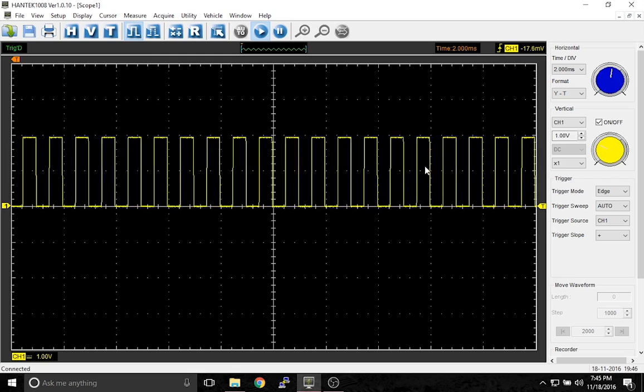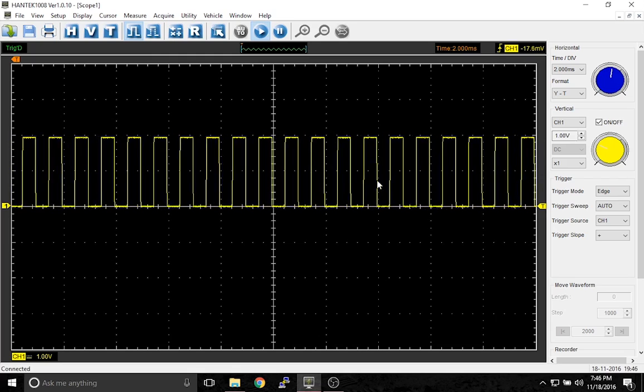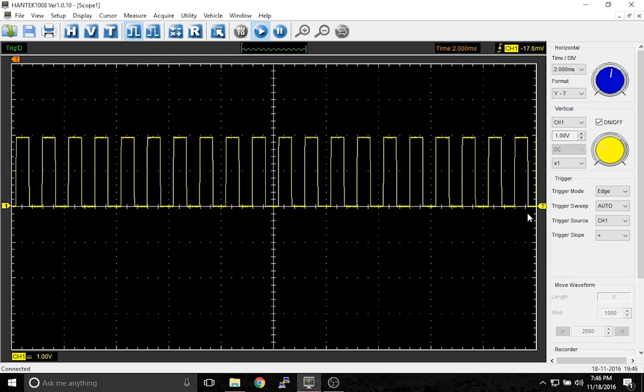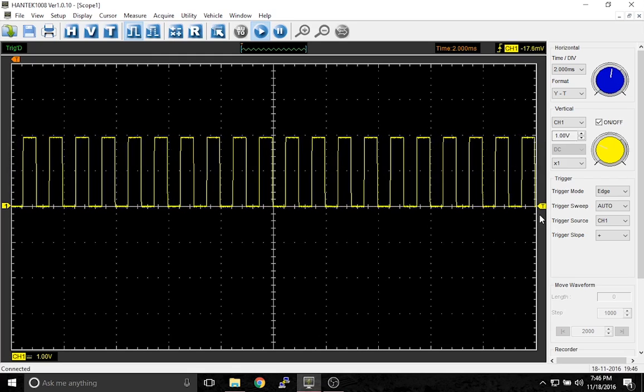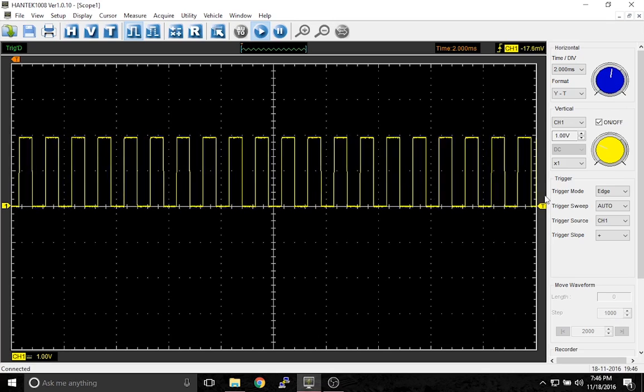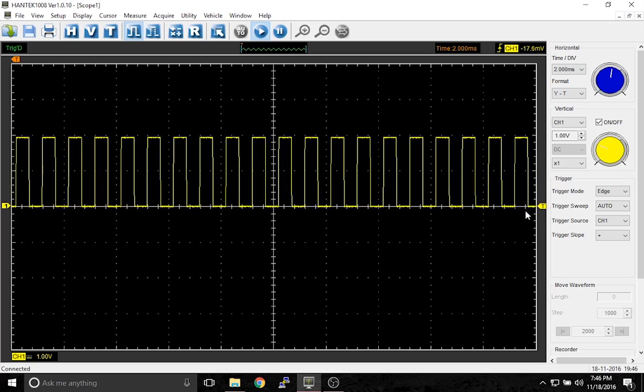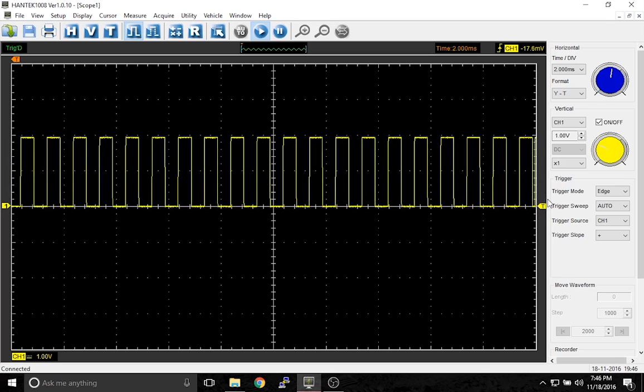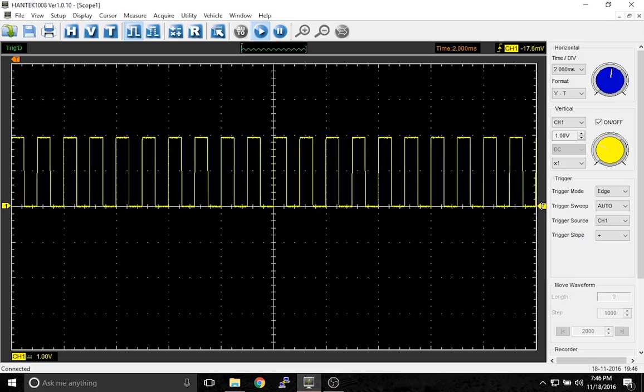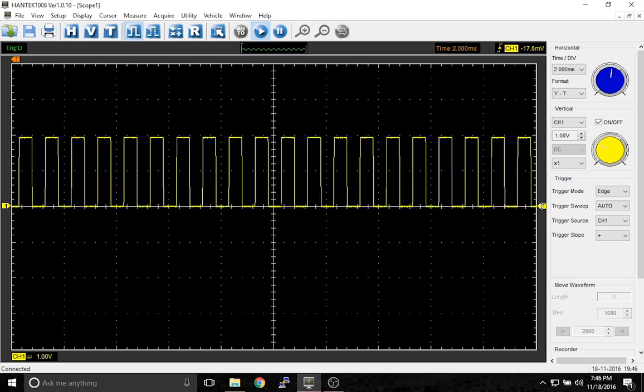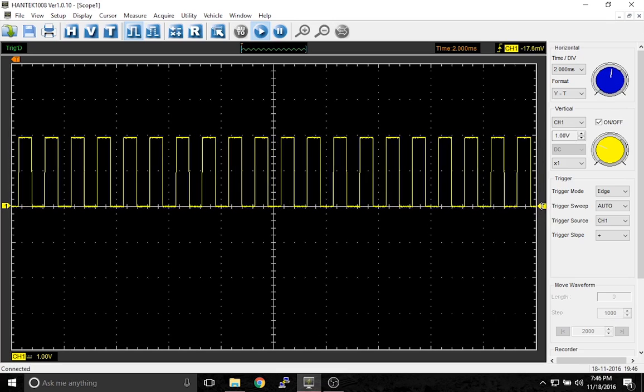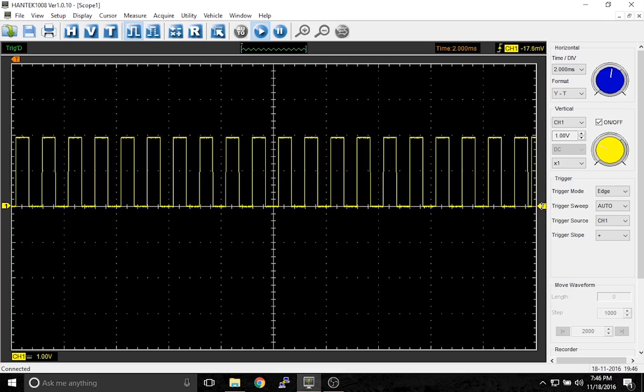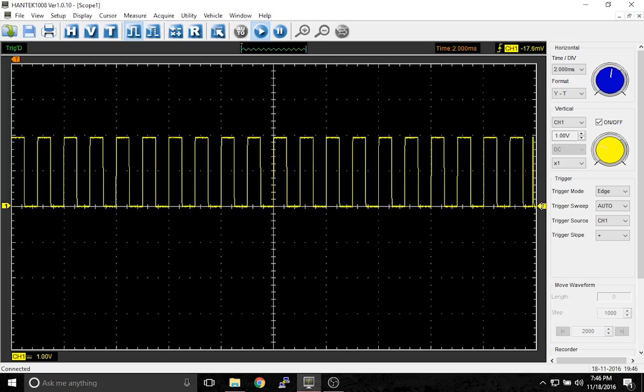The first thing we're going to do is keep this waveform still. And the way you do that is by setting a trigger. The trigger is this little yellow arrow here. What this does is it tells the scope when you want to start drawing the waveform.